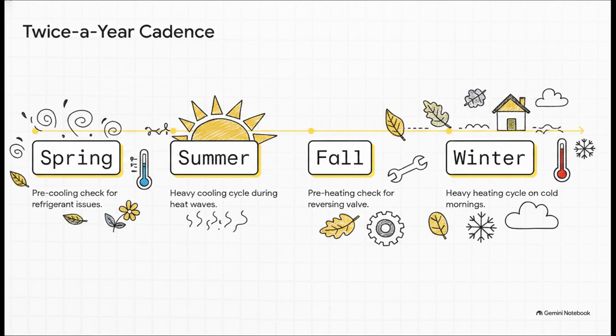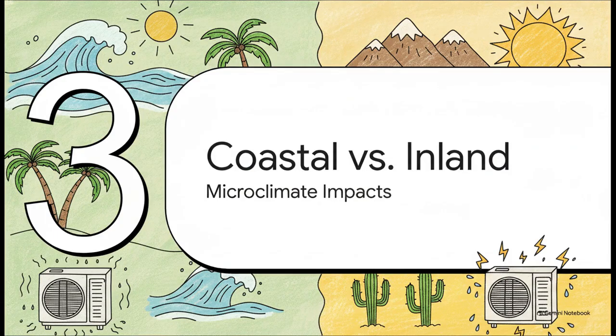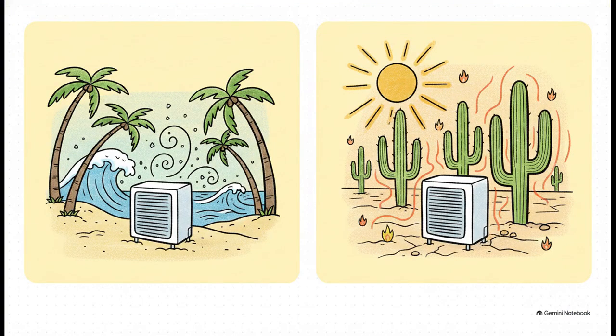That's going to catch a faulty defrost board or a sticking reversing valve before a chilly 40-degree December morning leaves you totally shivering in the inland valleys. Which brings us to Section 3, coastal salt versus inland heat. I want you to visually divide San Diego in your mind. On one side, we have our coastal areas, places like Solana Beach, Encinitas, and Imperial Beach.